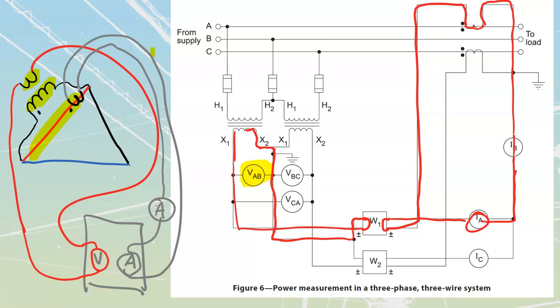We do see a couple of fuses on the high voltage side, but that's just there for protection if we have any sort of fault, because it's a high voltage installation. On the CT, you don't see any protection because the CT secondary should never be open, whether that's from an electrician doing something wrong or from a blown fuse. It would be catastrophic to the system, so we just don't want to see that.